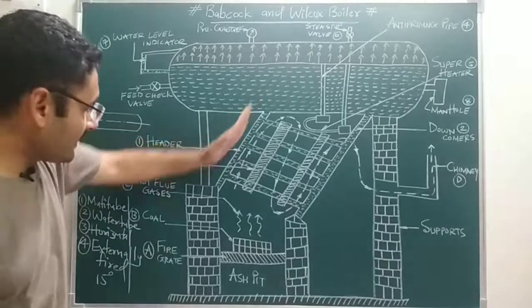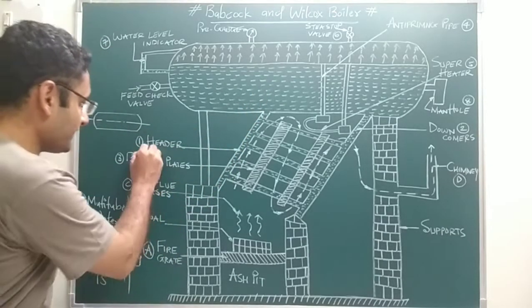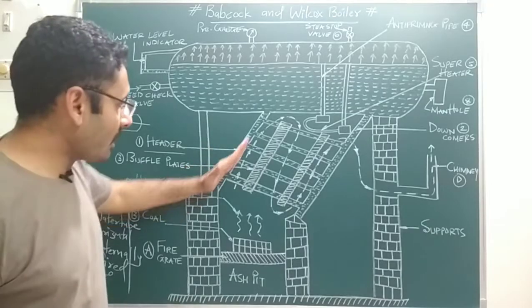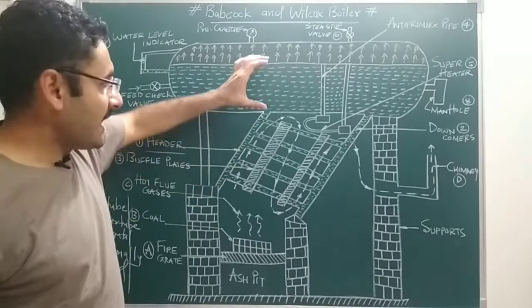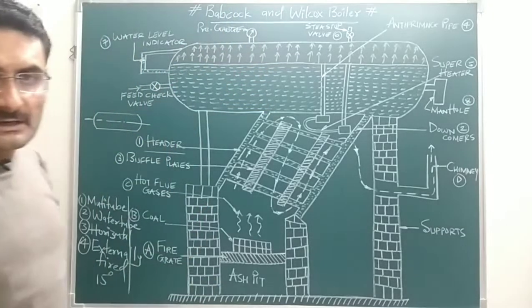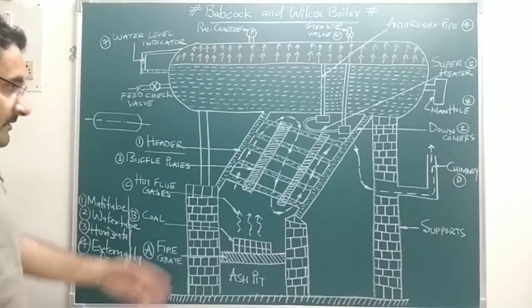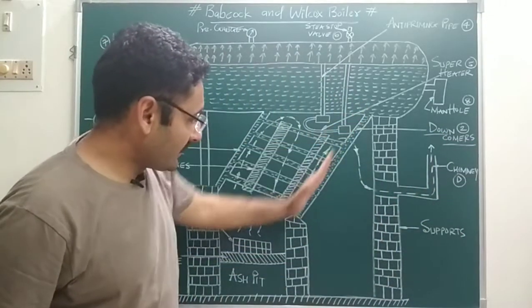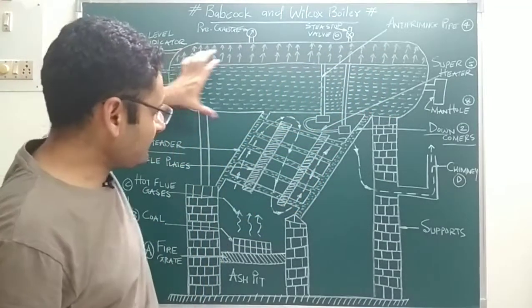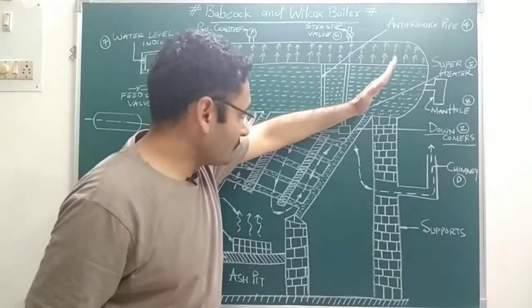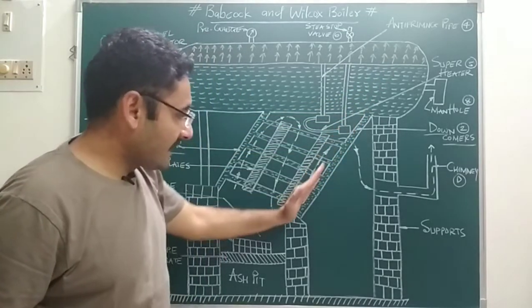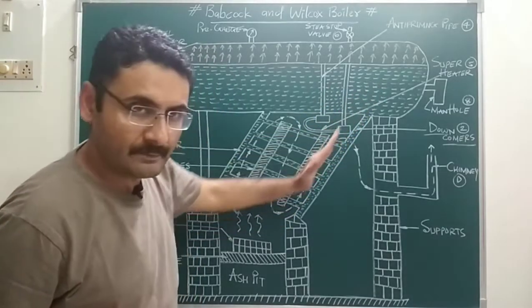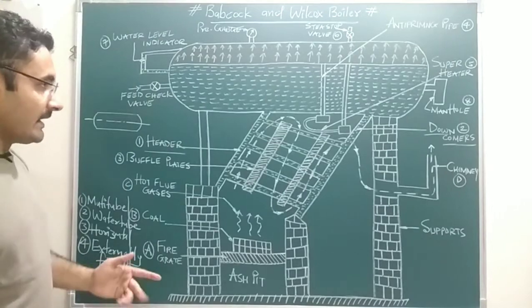Now, the important parts. The first part is the header — a tube through which hot water moves upward and enters the boiler shell, converting into steam. The next important part is the downcomer — an inclined tube through which cold water present inside the boiler shell moves in the downward direction. With the header, hot water moves up; with the downcomers, cold water moves down.